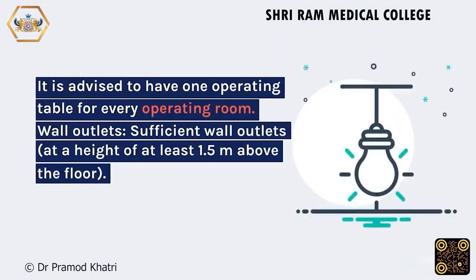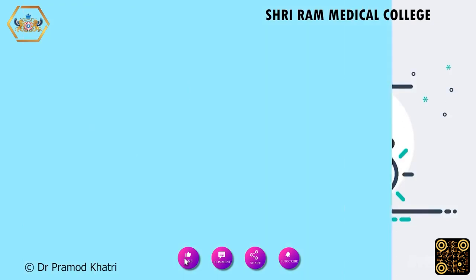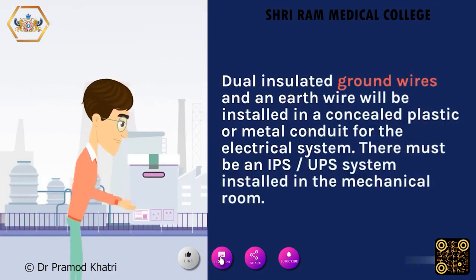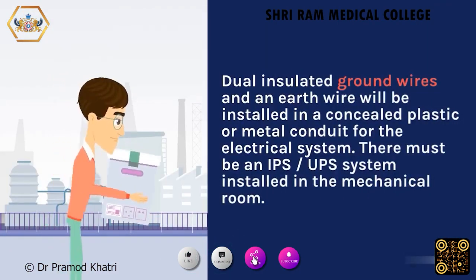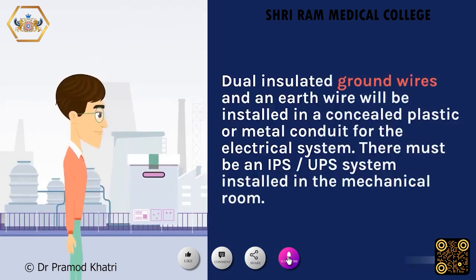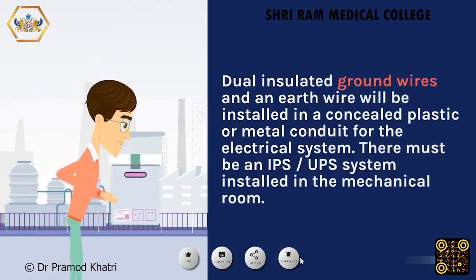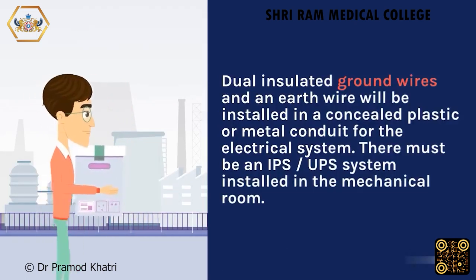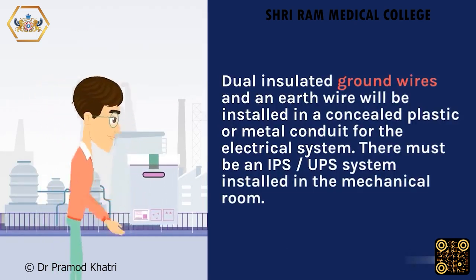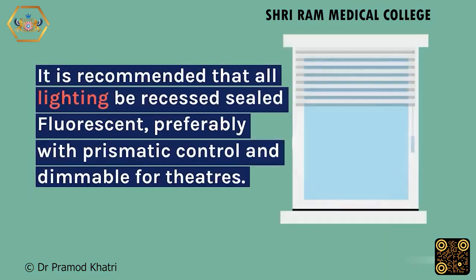It is advised to have one operating table for every operating room. Wall outlets, sufficient wall outlets, at a height of at least 1.5 meters above the floor. Dual insulated ground wires and an earth wire will be installed in a concealed plastic or metal conduit for the electrical system. There must be an UPS installed in the mechanical room. It is recommended that all lighting be recessed sealed fluorescent, preferably with prismatic control and dimmable for theaters.